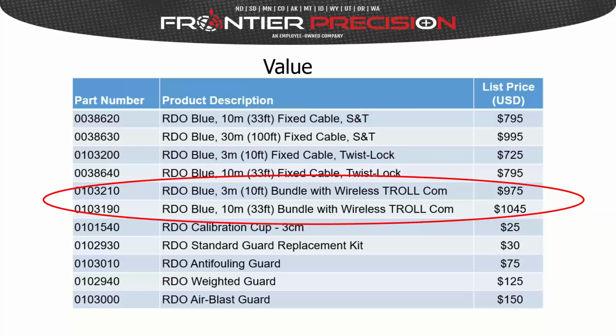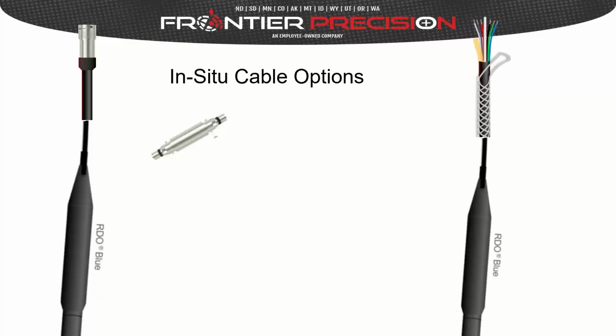And then beneath that, you can just see some of the prices for the options and accessories. Now, when we were looking at the price there, you saw that there were what we call twist connect or twist lock cables and stripped and tinned cables. So on the right, it shows an example of the stripped and tinned cables. So you just get the cable with bare wire leads, the assumption being that you would have terminal posts on your data logger or your SCADA PLC that you would wire that directly into.